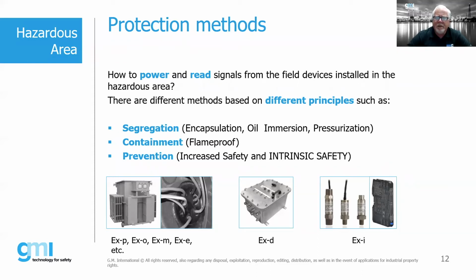So when we talk about these three concepts, segregation, encapsulation, oil immersion, pressurization, when we're talking about segregation, we're segregating one or more of those legs of the triangle from each other. For example, if we pressurize an enclosure, we're separating the flammable mixture, the flammable gas or vapor, from the source of ignition. That's segregation. Flameproof is where we contain it. We're assuming we're going to have all three legs of that triangle present, and when we have an arc or spark, it's okay because we're containing it within a flameproof, or what we might call explosion-proof, type enclosure.